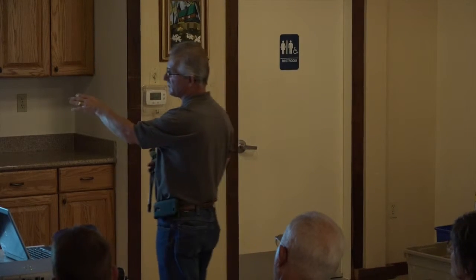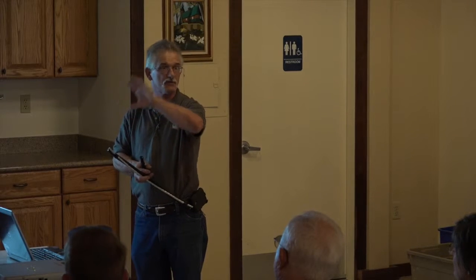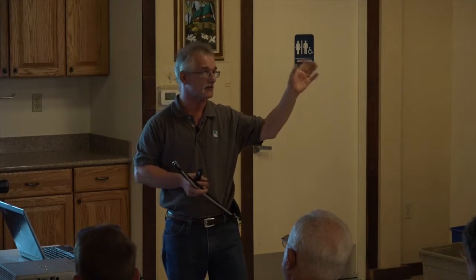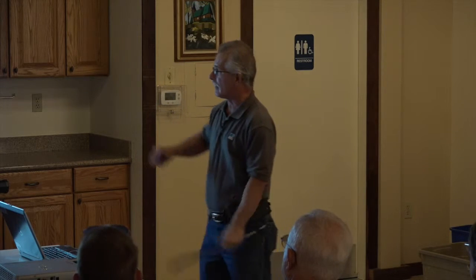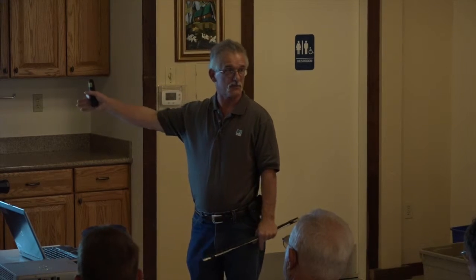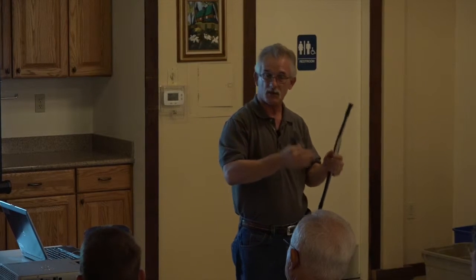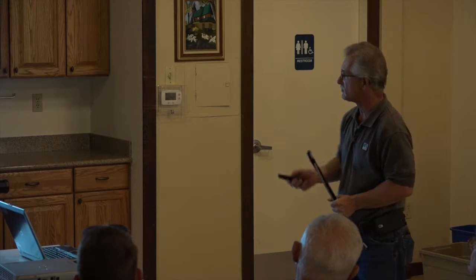So what happens is the electricity comes from the power source onto our transmission lines. The transmission lines are anywhere from 60 to 500,000 volts—these are the huge towers you typically see along open space areas that could come through town. Then the transmission power comes into a substation, where it drops the voltage to a distribution system. That distribution system is 4,000 to 21,000 volts—that's the wood poles you see around the neighborhood, our distribution system.